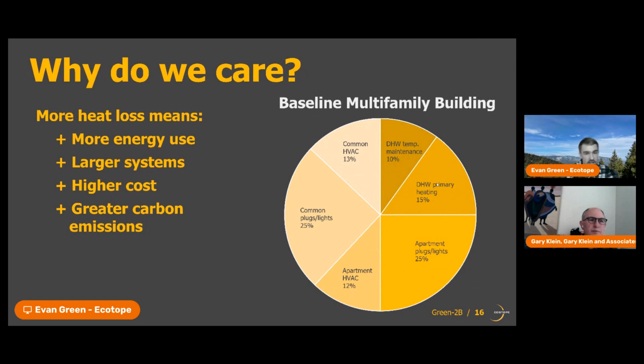But the way we size heat pump water heaters is we basically look at them like trickle chargers that charge the hot water storage. The hot water storage is what satisfies those peak loads, while the heat pumps run 16 to 20 hours a day to satisfy the average hourly usage that makes up the total daily usage. So these heat pumps are slowly humming along, recharging these tanks. And if we drop in a temperature maintenance load or delivery heat loss that almost accounts for half of the overall heating load, now we have to upsize these heat pumps by about 50% to accommodate those loads. Recovery is not cheap with heat pump water heaters, so that's going to add a lot of capital cost, as well as a lot of energy usage to your building. So we need to decrease these losses so we can decrease system sizes as well as energy usage, which in turn will decrease the carbon emissions from our buildings.